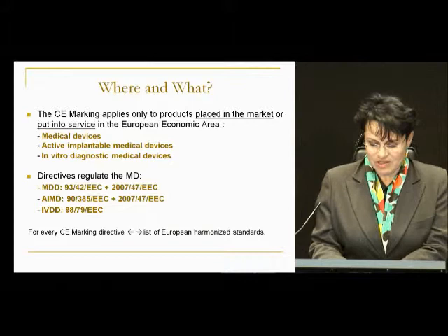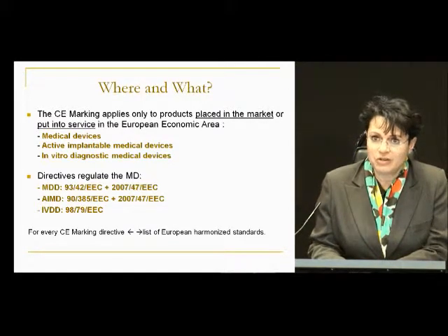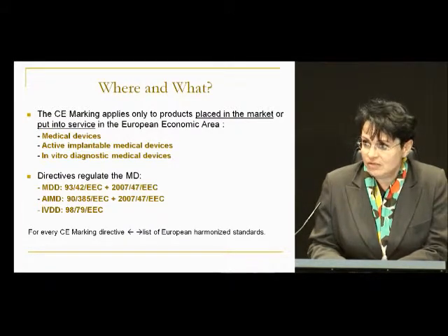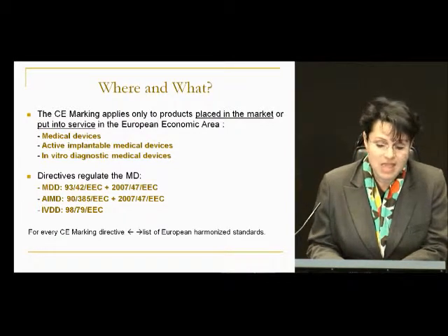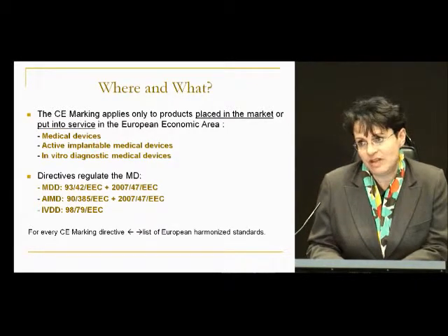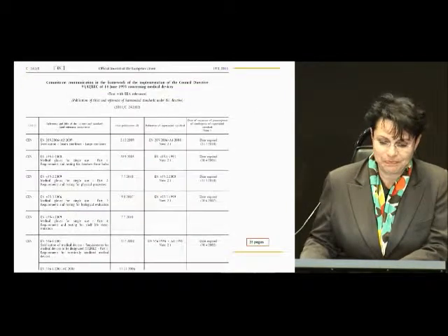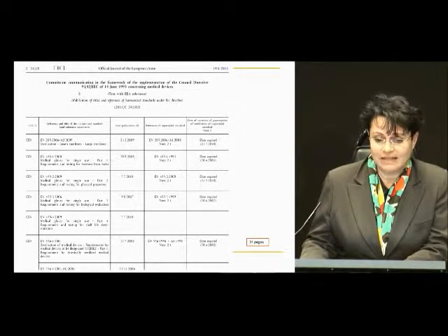So for every CE marking directive, you have harmonized standards. It means that the manufacturer has to implement standards which are published on the European market through the official journal, and these standards are audited by the notified body every time a first CE marked product is placed on the market. Just for example, part of the list which relates to the medical device, so the main directive, I will use this directive for my presentation.